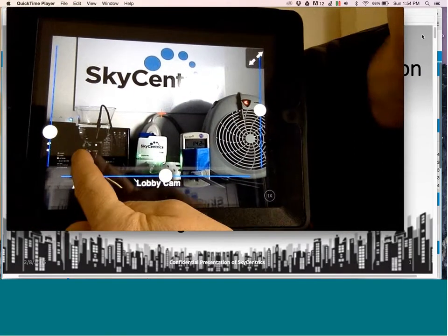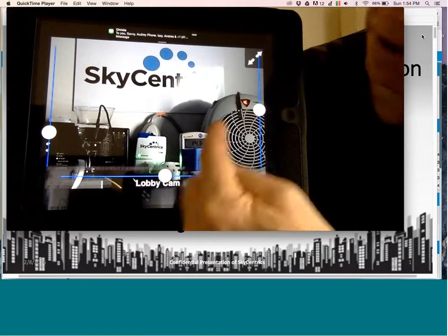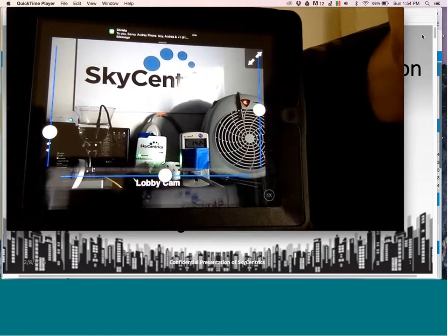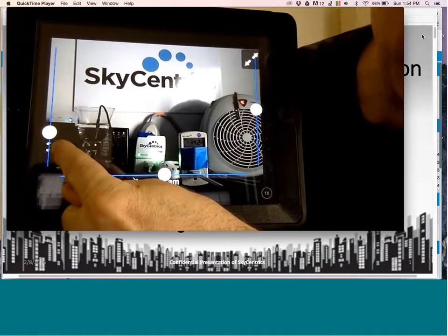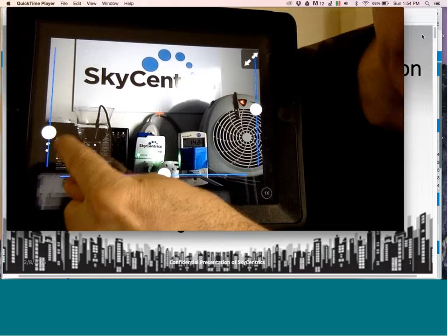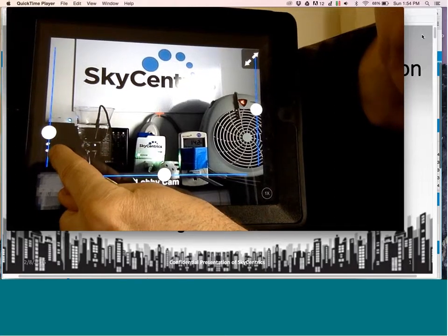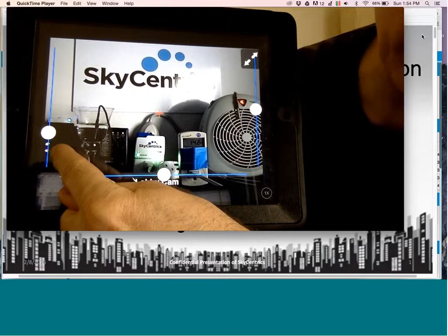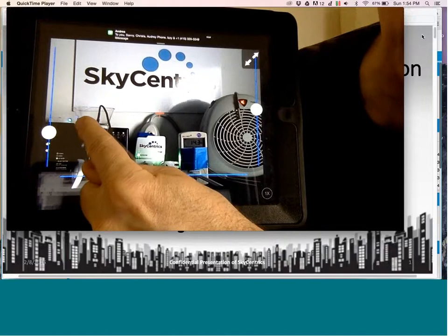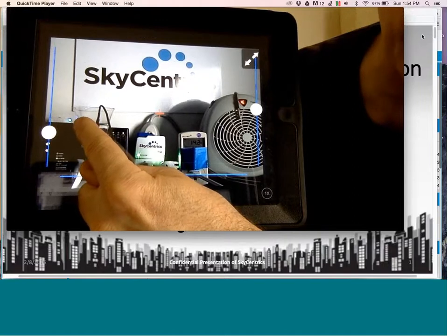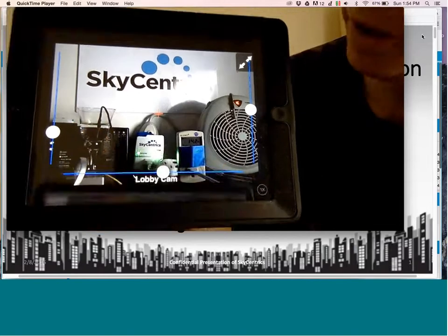So this is an Emerson water heater switch. There's a smart plug plugged into it. It's going to a watt node and then to a heater so that we can actually energize the water heater. And when we run our DR event, notice that there's two lights right over here. There's a green light, you can't see the color, but it's far away from the yellow light, which is showing that it's connected to the internet. There's a CTA 2045 SkyCentrics radio module that's blinking right above it and plugged into the Emerson water heater switch.